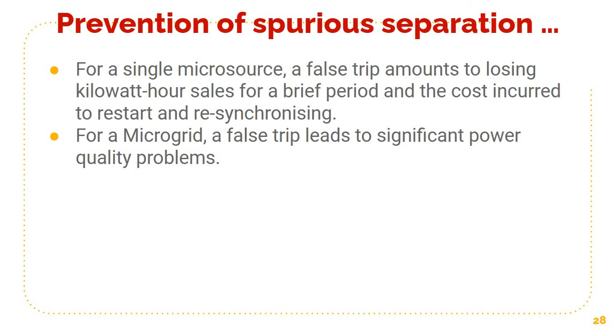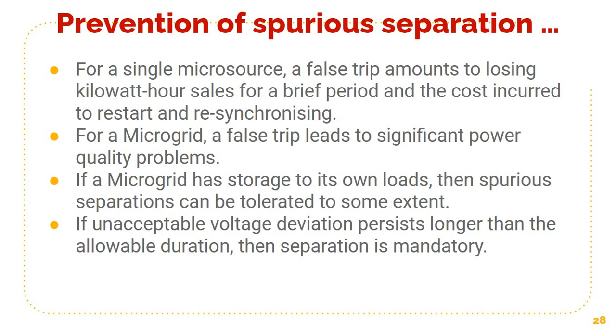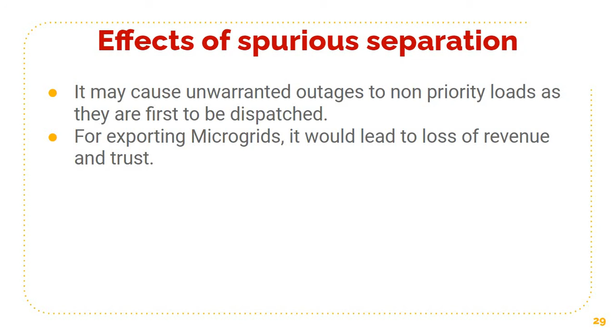If a microgrid has enough storage, then spurious separations can be tolerated. So if a voltage deviation persists longer than the allowable duration, for example, more than 3 cycles, then there is no other way other than going for a separation. So the effects are unwarranted outages to non-priority loads, and for exporting microgrids, it leads to loss of revenue and trust. The trust is more important. If you cannot supply energy as per the contract, then it affects the trust.